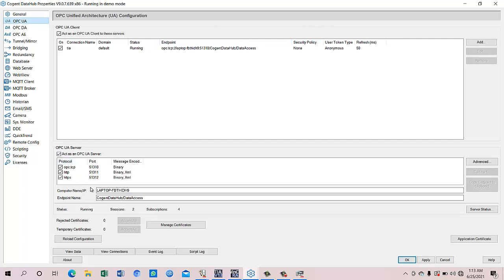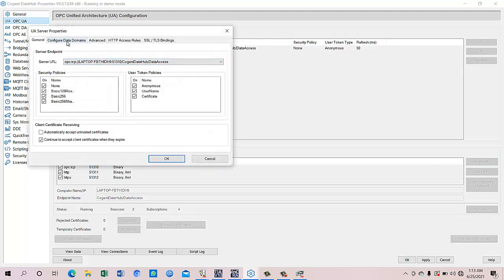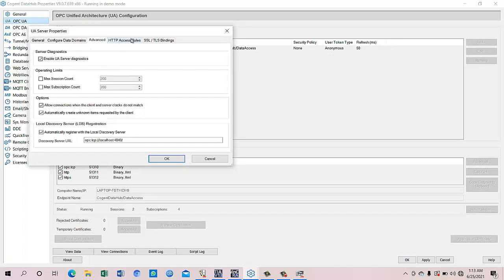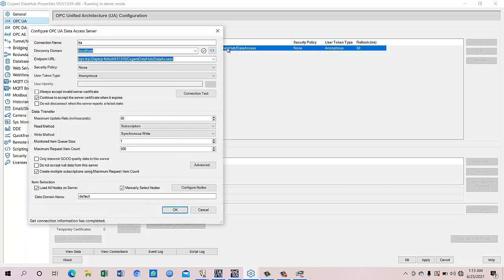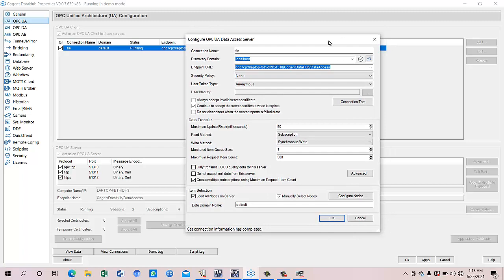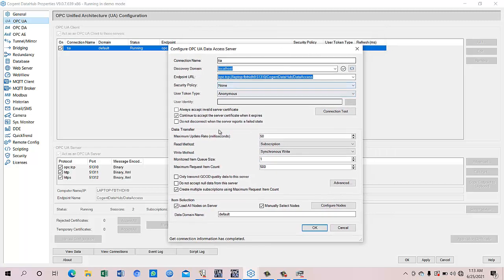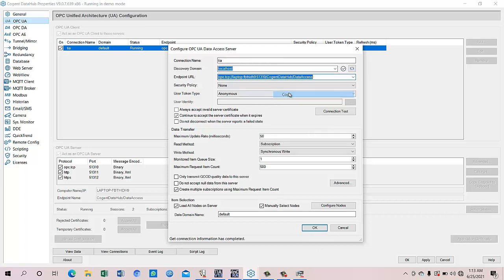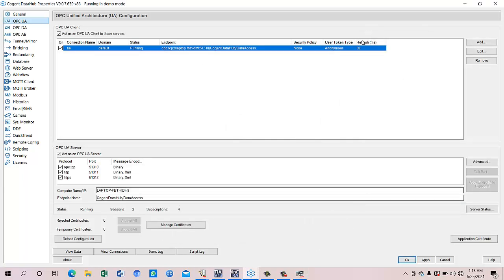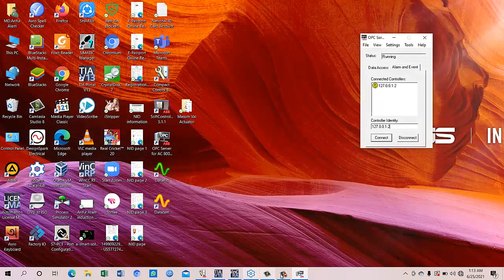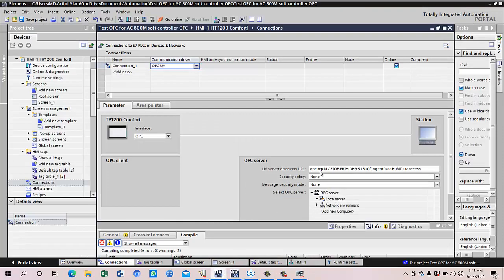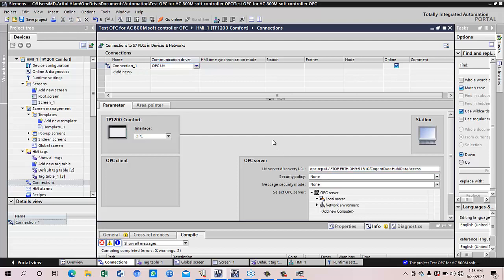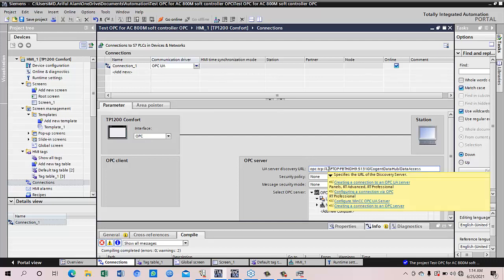Here you can see my laptop is the OPC UA server name and the endpoint name is Cogent Data Hub by data access. So this is the OPC UA server name. So for this OPC, this is also acts as a OPC client. This is the endpoint URL that has to be copied and this thing has to be copied and it has to be set as a connection name over here and you paste it over here. So the OPC UA is connected now to the WinCC TIA Portal.